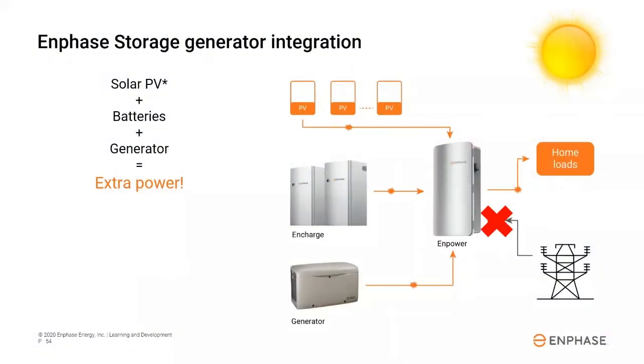Enphase storage generator integration eliminates the transfer switch. The generator is tied directly into the Enpower smart switch. The generator, battery storage, and solar PV can all operate simultaneously. With all three power sources operating together during a grid outage, the home will have the combined power to start and run large electrical loads. For example, a homeowner could run their AC or their electric dryer only during the day when all three power sources are operating, and then conserve energy at night when running only off of battery power.